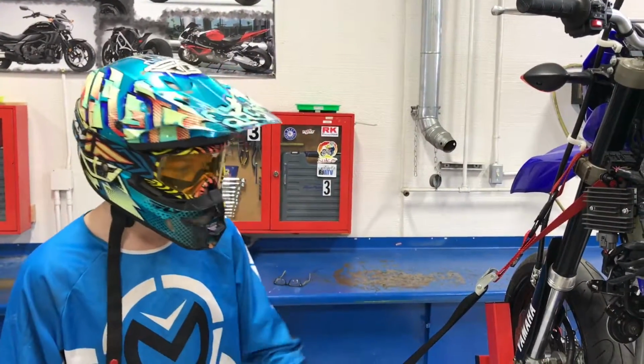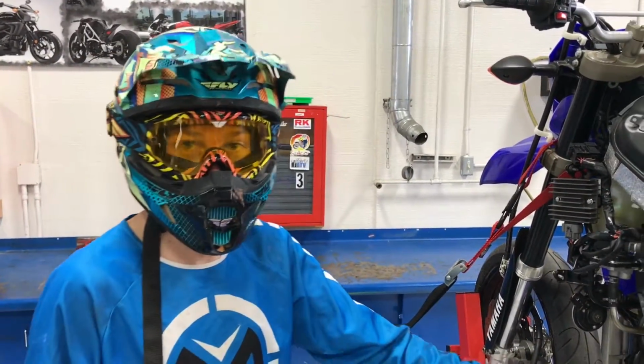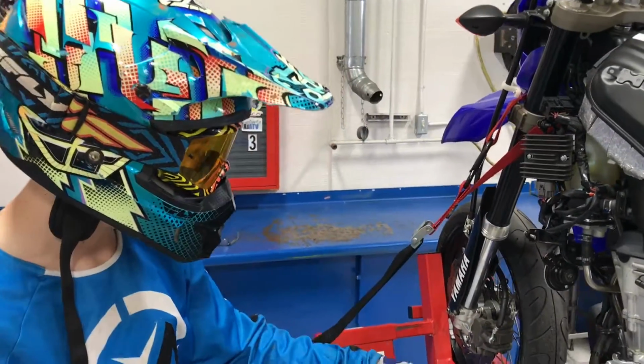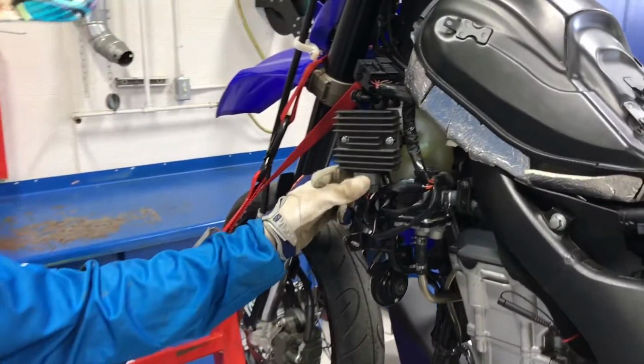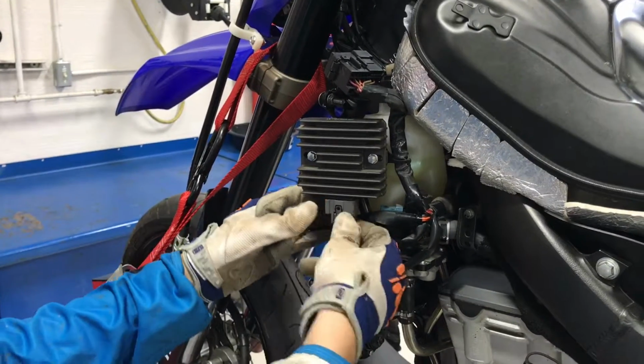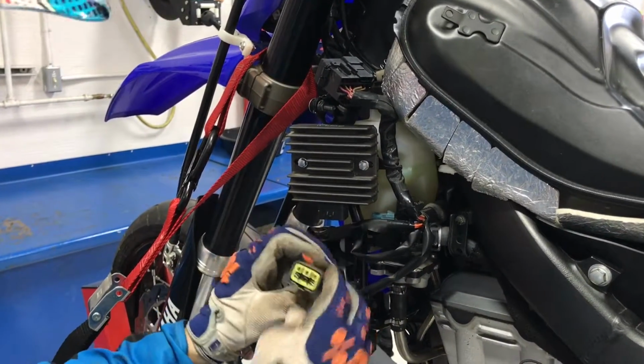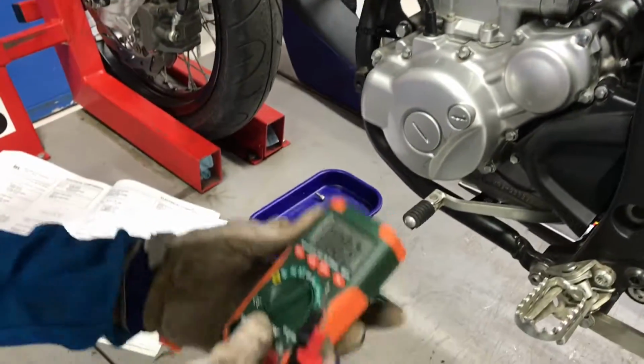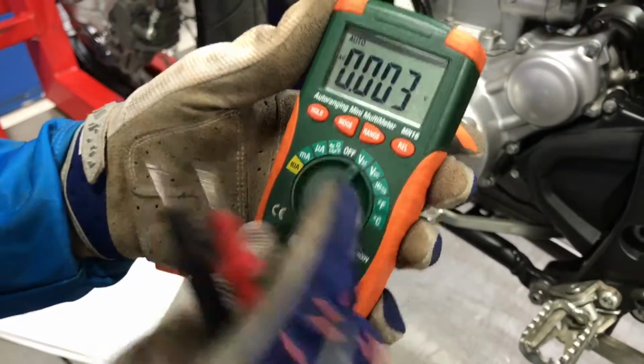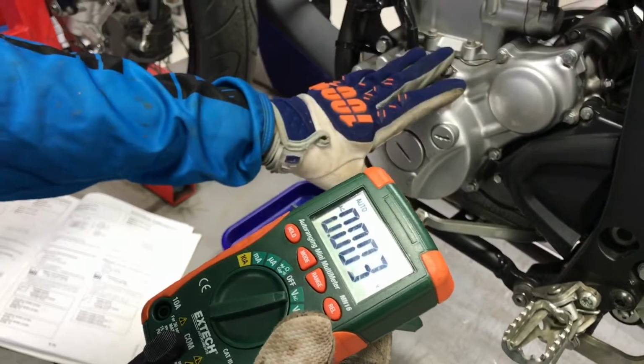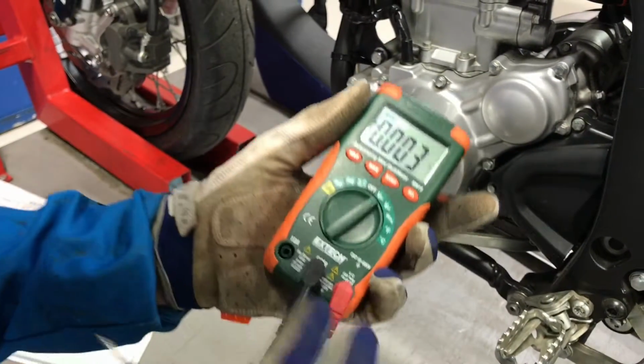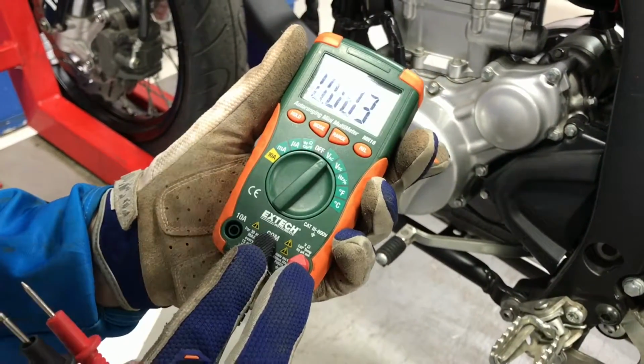Alright, so moving on, we will be checking the voltage coming from our stator coil. To start that, you need to remove the coupler coming from your stator coil from your voltage regulator. While doing this, you would need to have your meter set at AC voltage, because AC voltage is produced from the stator coil.